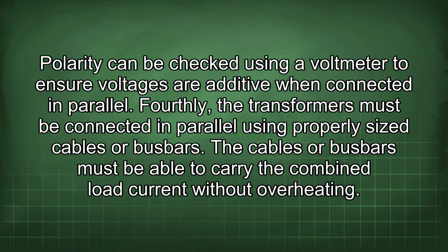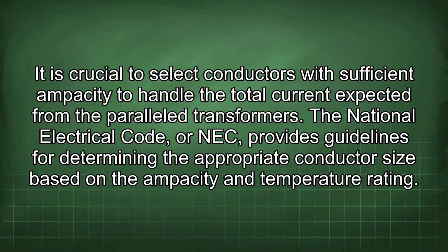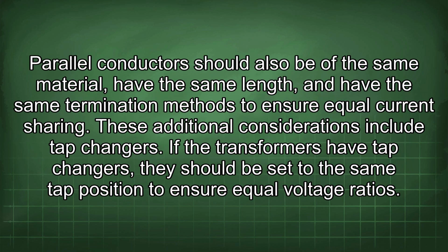Fourthly, the transformers must be connected in parallel using properly sized cables or busbars. The cables or busbars must be able to carry the combined load current without overheating. It is crucial to select conductors with sufficient ampacity to handle the total current expected from the parallel transformers. The National Electrical Code, or NEC, provides guidelines for determining the appropriate conductor size based on the ampacity and temperature rating. Parallel conductors should also be of the same material, have the same length, and have the same termination methods to ensure equal current sharing.